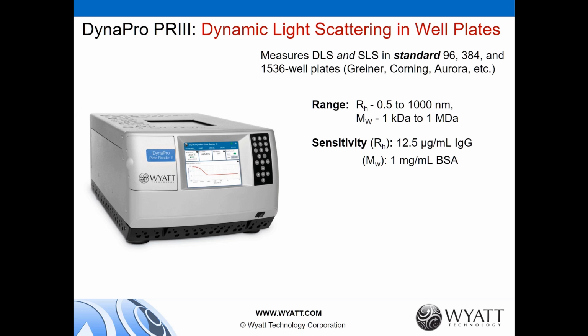The range for size is 0.5 to 1,000 nanometers in RH, and the range for molecular weight is a kilodalton up to a megadalton. The sensitivity for hydrodynamic radius is comparable to measurements in cuvettes, so it's 12.5 micrograms per milliliter of IgG. And the sensitivity for molecular weight is not quite as good, so it is relatively challenging to make excellent SLS measurements in a plate at the level that you might be used to from SEC-MALS. So the lower limit here is about 1 mg per mL of BSA, which works out to approximately 0.4 mg per mL of IgG.